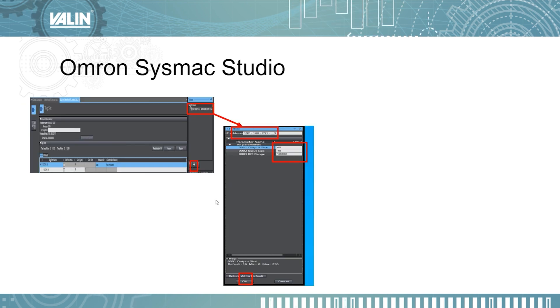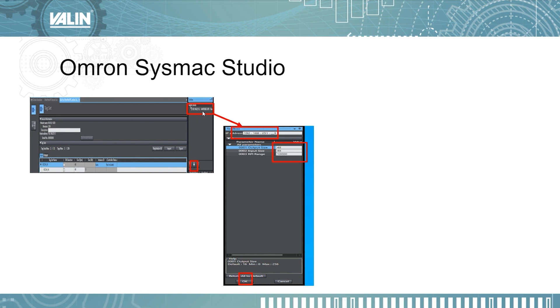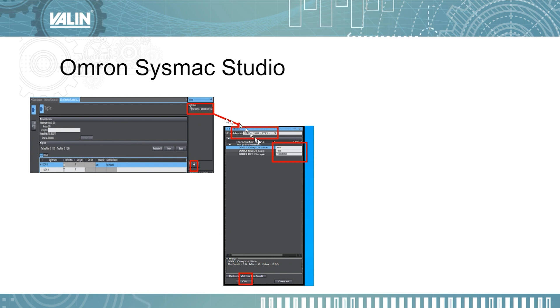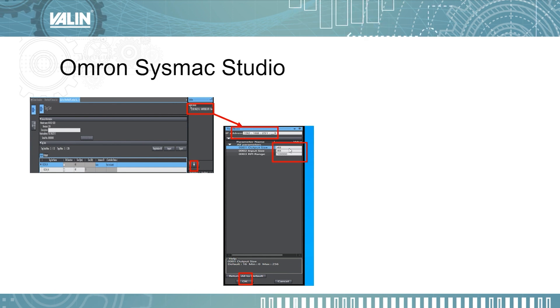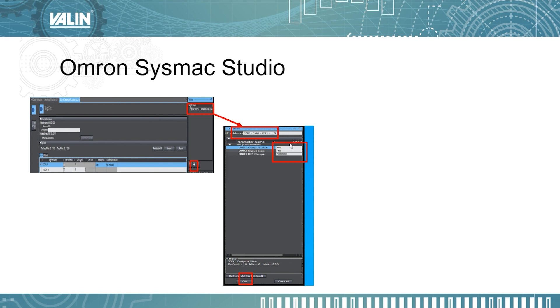Then on the right side, select 192.168.251.3, which is your Archon device, and click Add, then select it. Once you've done that, go in and change the number of bytes to 48 bytes for input and 48 bytes for output, then click OK. This is very important because it configures the correct data size for the Archon system that you have.